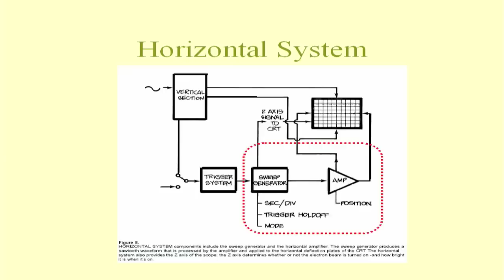Okay. So in general, anytime we're moving the beam across the screen, we call that a sweep. So how fast are we sweeping that beam across the screen? And how do we do that? The earlier scopes, like the Dumonts, and some of the other scopes you have around here, some of what we call the service type scopes, use what's called a recurrent sweep technology. Meaning that that horizontal sawtooth waveform that's used to drive the beam across the screen and then reset it and drive it across the screen again is a continuously running sawtooth oscillator. So it just keeps going along.